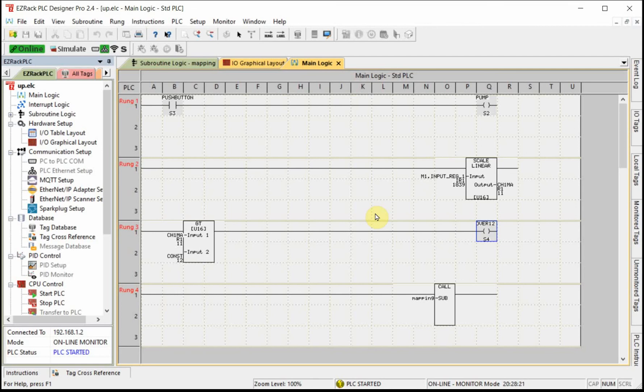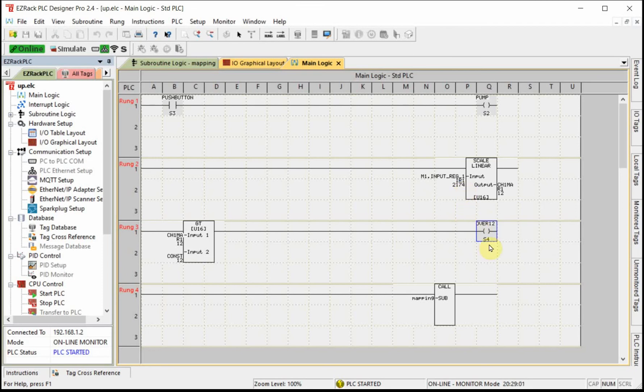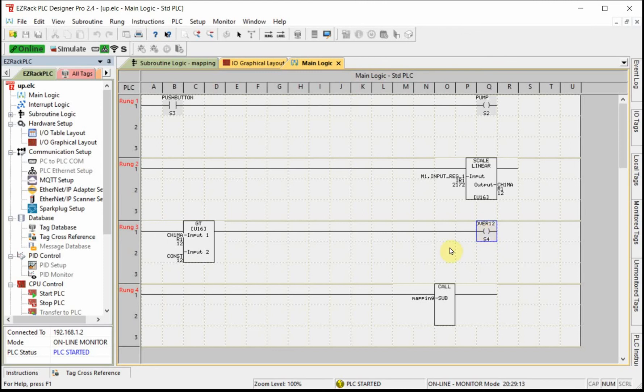Right now we're talking about very basic controls — turning on outputs, doing a little bit of math. One thing I notice is that if I turn the pot up to around 12.95 it flickers, because I'm bouncing above and below the threshold. If I put a filter on this — say, a half-second delay before it turns on — I think I can avoid that chattering.